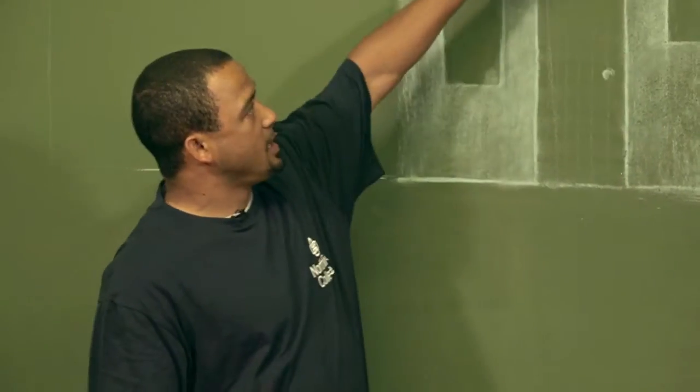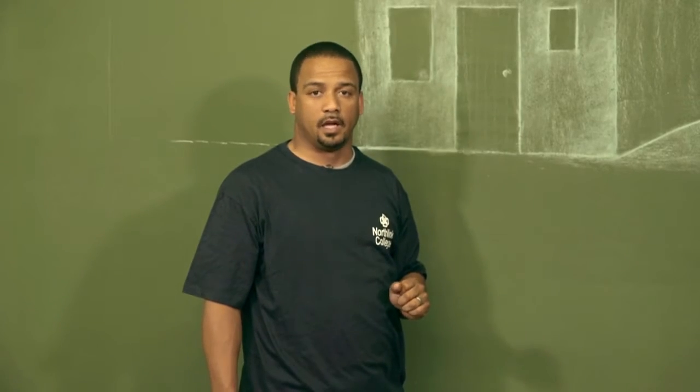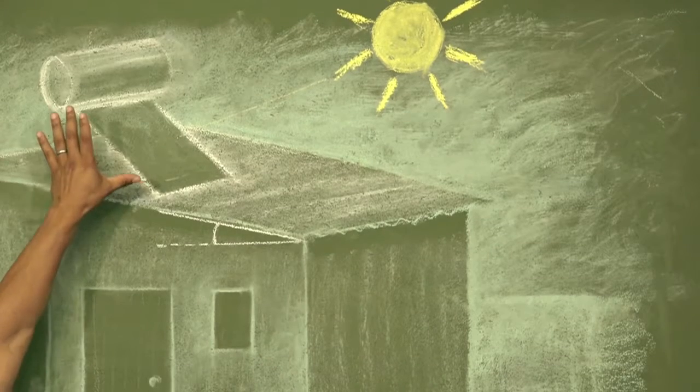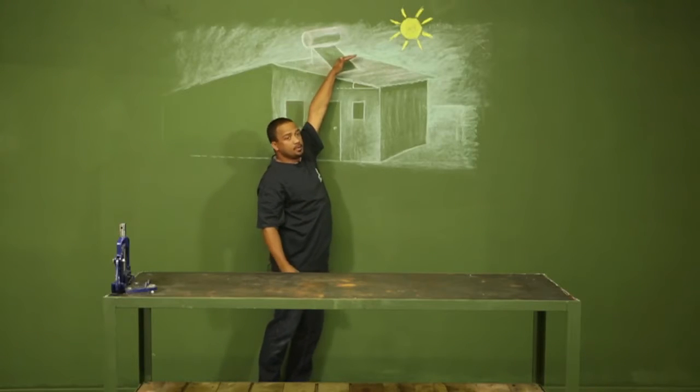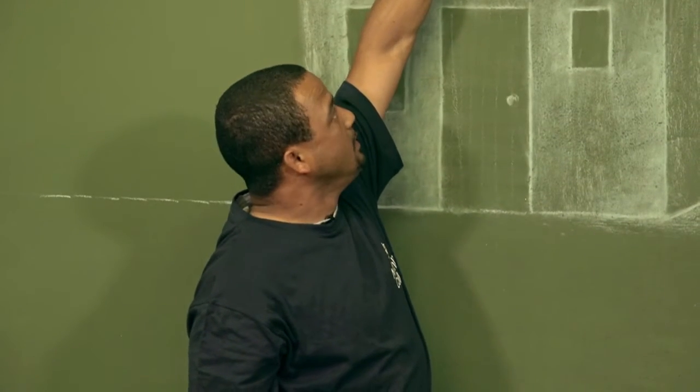Our solar thermal installation is now complete in accordance to our prescribed manufacturer guideline, and we've ensured that the position of our solar collector is perpendicular to the sun. This ensures that we get maximum radiation onto our collector, which will improve the efficiency of our system.